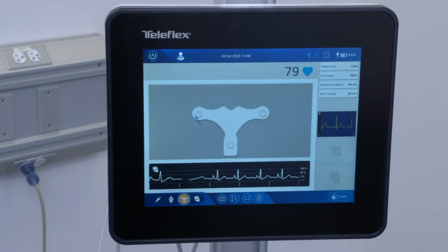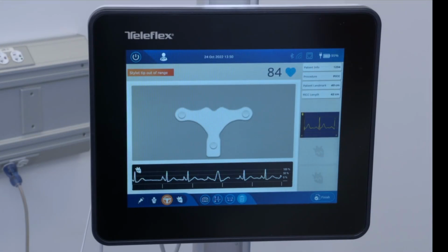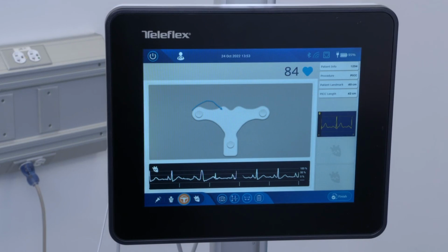The blue tip tracker technology line illustrates the catheter pathway as it approaches and descends towards the SVC and allows easy, real-time adjustments during PICC navigation. Verify that the P wave on the intravascular ECG waveform is present, identifiable, and consistent. The T-piece has approximately a 22 centimeter or 9-inch sphere of visual navigation from the center of the T-piece. If the stylet is out of magnetic range of the T-piece, an alert will appear on the screen.